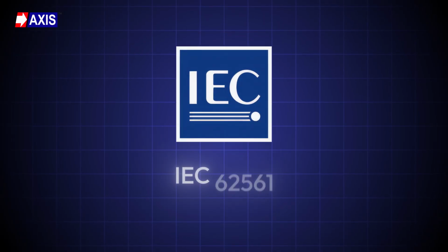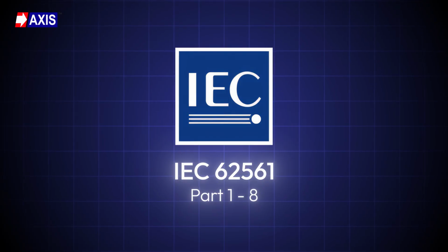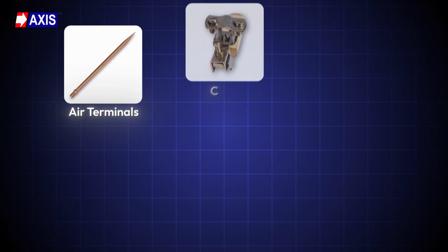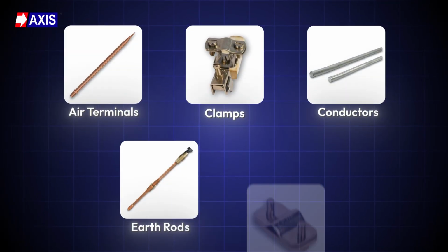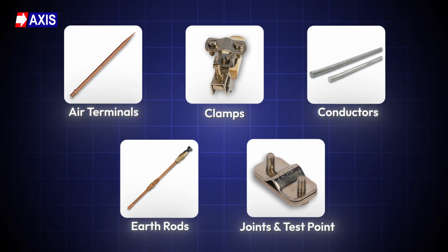IEC 62561 Part 1 to Part 8. This standard defines the performance and testing requirements for all components in an external lightning protection system. It covers air terminals, clamps, conductors, earth rods, joints, and test points. These standards apply across your system, covering materials, installation methods, and component testing.